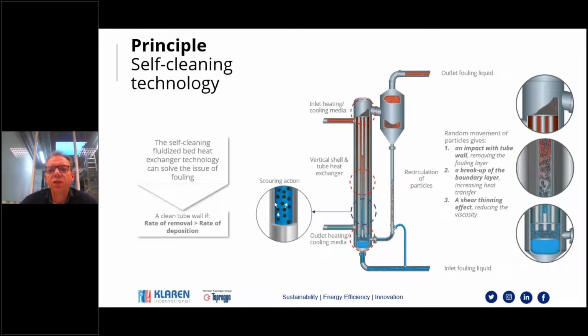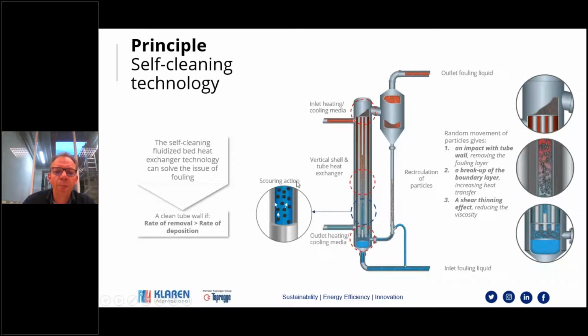And at the end of the heat exchanger, we will separate them again from the liquid, such that we can recirculate the cleaning particles back to the inlet, to the downcomer, which you see here on the right side. And the cycle can repeat itself, whereas the liquid that is heated, or in other applications it's cooled, will flow to the next step of the process. So the core is fluidization of cleaning particles at the inside of this tube.